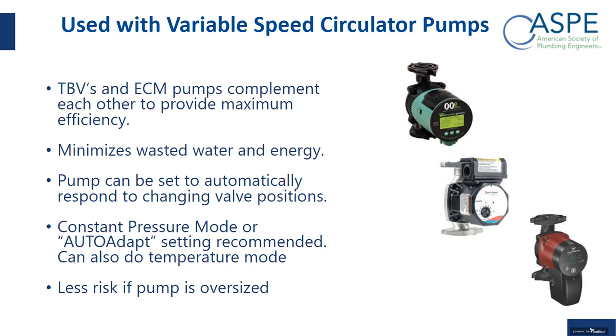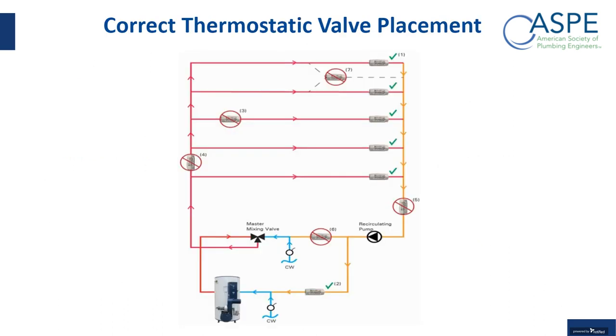What I like personally about interfacing a thermostatic valve with a variable speed pump is that now you can basically oversize the pump and not have to worry about excessive flow velocity. Because if you did oversize the pump and you start getting the higher pressure drops, you're going to basically start slowing down the RPMs of the pump. So I think that takes away some concerns that you may have with excessive flow velocity. I think it's really a great way to optimize not only the use of energy, but also to help with more easily sizing the pump.